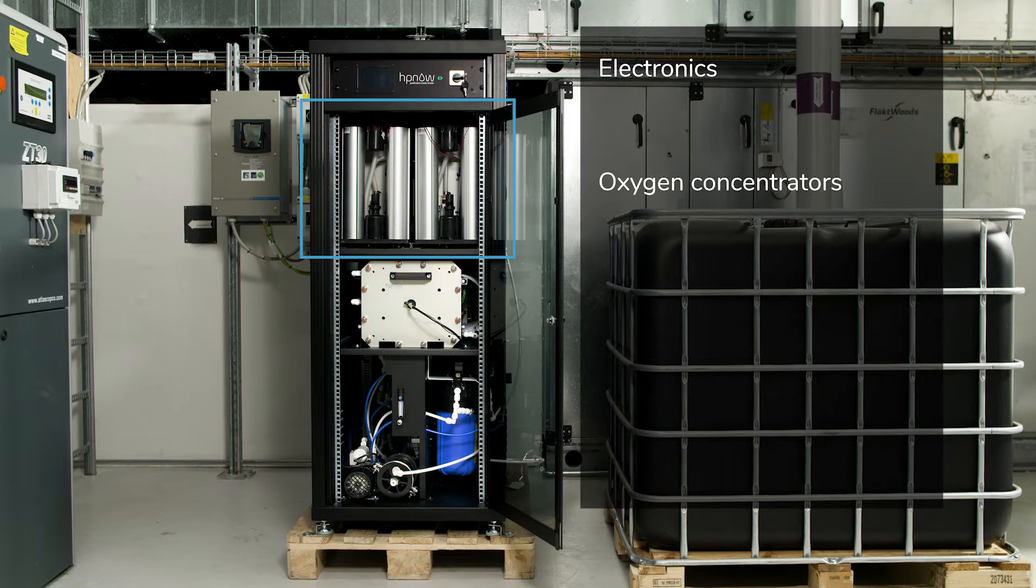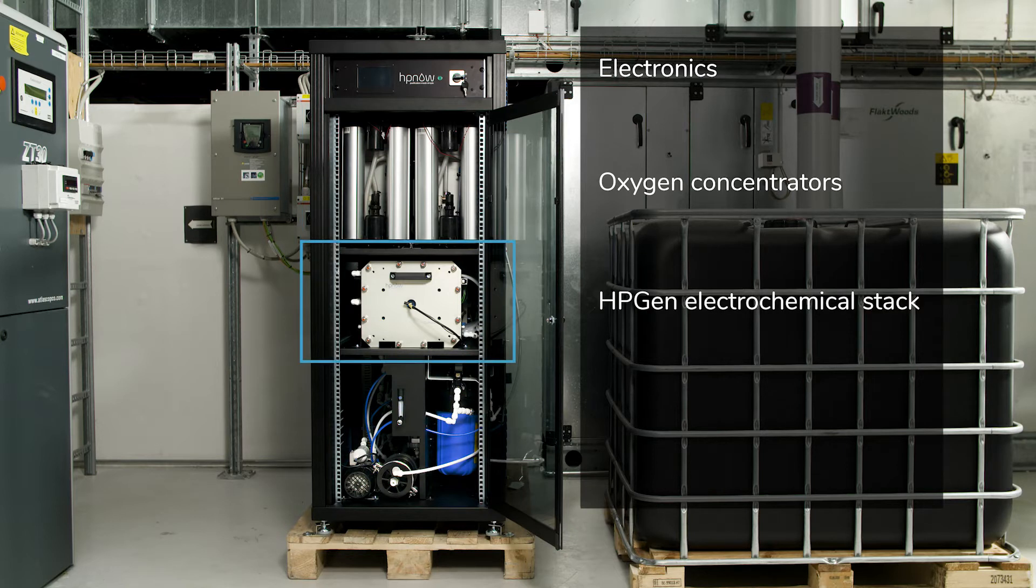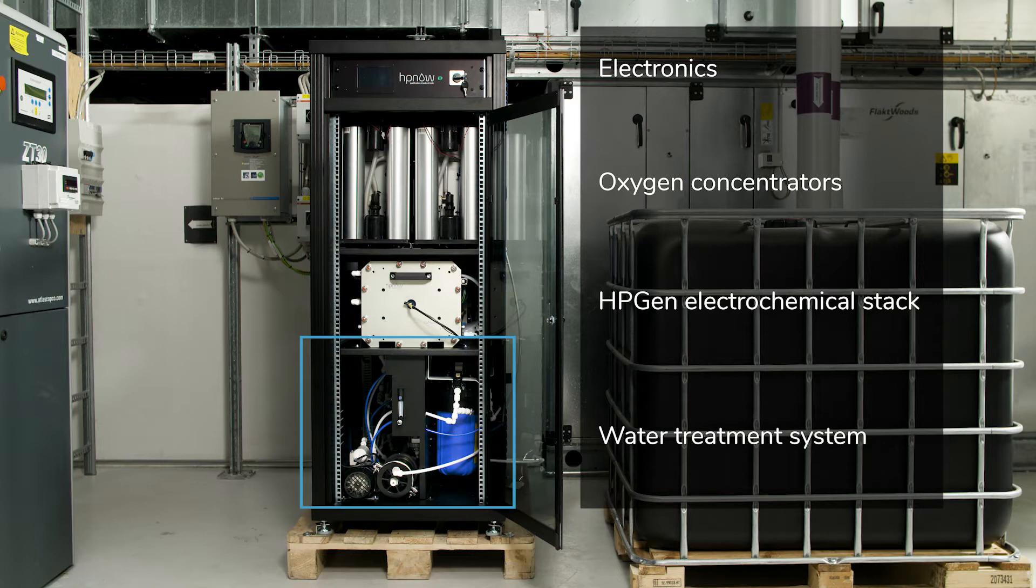Below the drawer are oxygen concentrators for oxygen delivery to the electrochemical cells. Underneath is the electrochemical stack, which combines water, oxygen, and electricity to produce the peroxide ultra-pure solution. Finally, in the bottom, a water pre-treatment system supplies deionized water to the electrochemical stack.